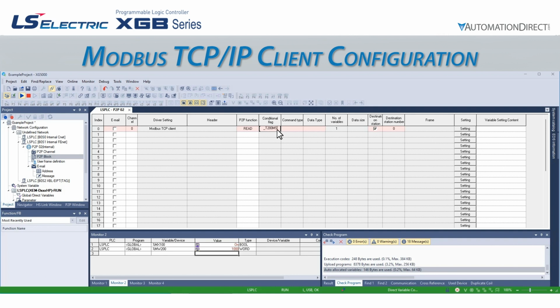For the command type column, we can select single to read or write a single bit or register, or continuous to read or write a range of consecutive bits or registers. We will select single for our read. The data type can be bit or word. If we wanted to do a coil or input function code, we would select bit. For any of the register function codes, we would select word. In our example, we wish to read the drive speed, which is a word register.